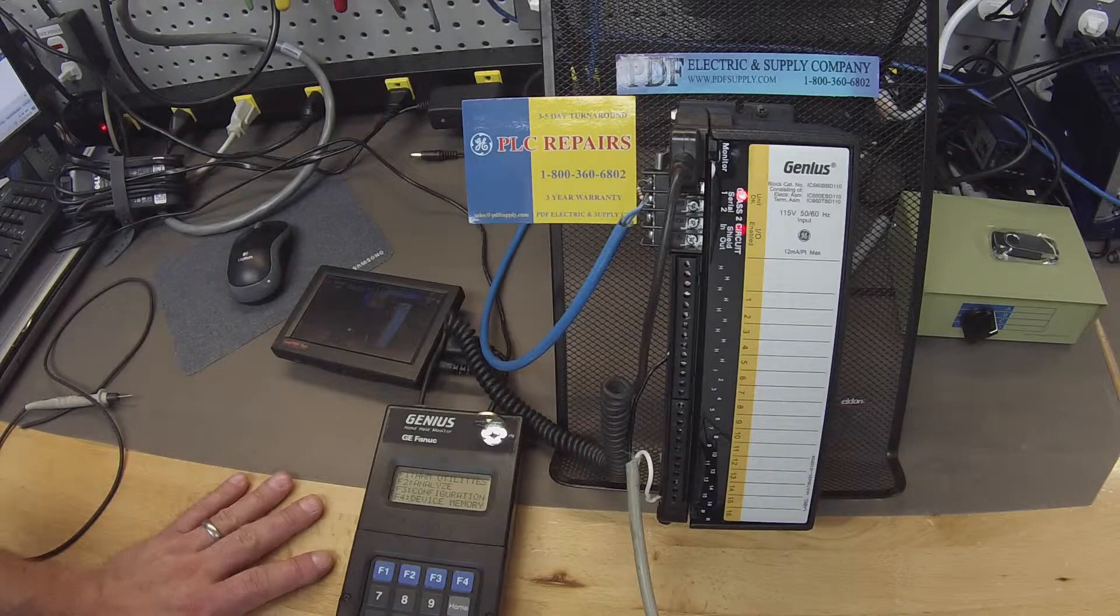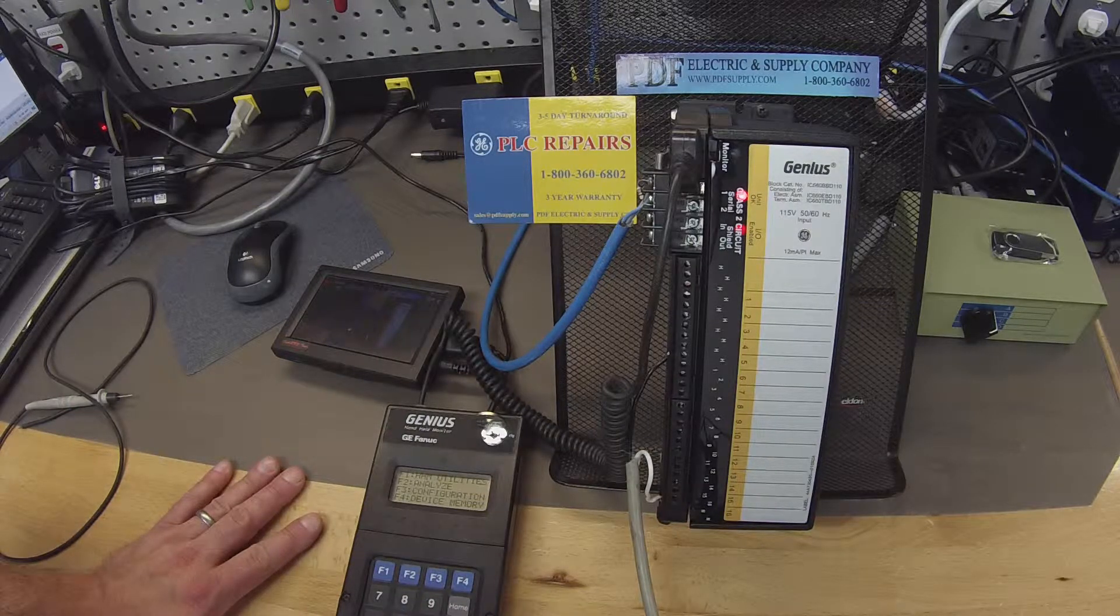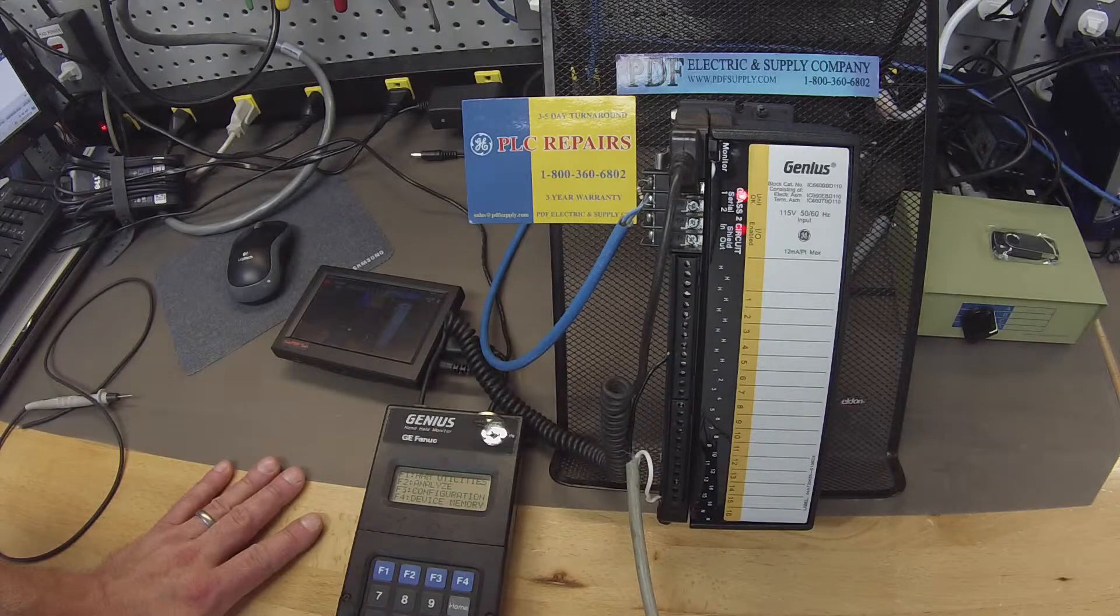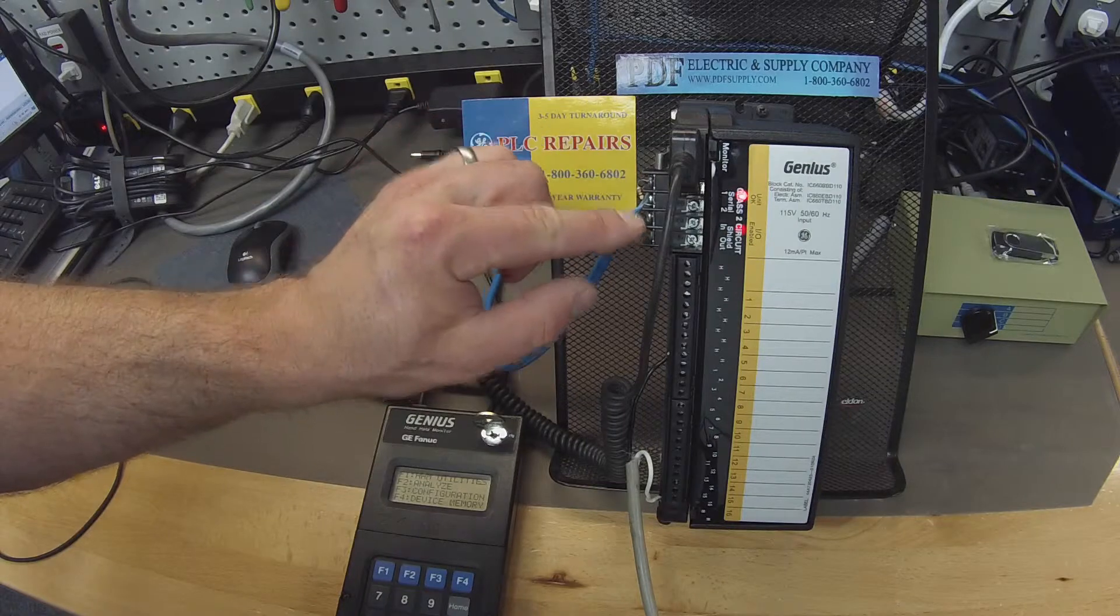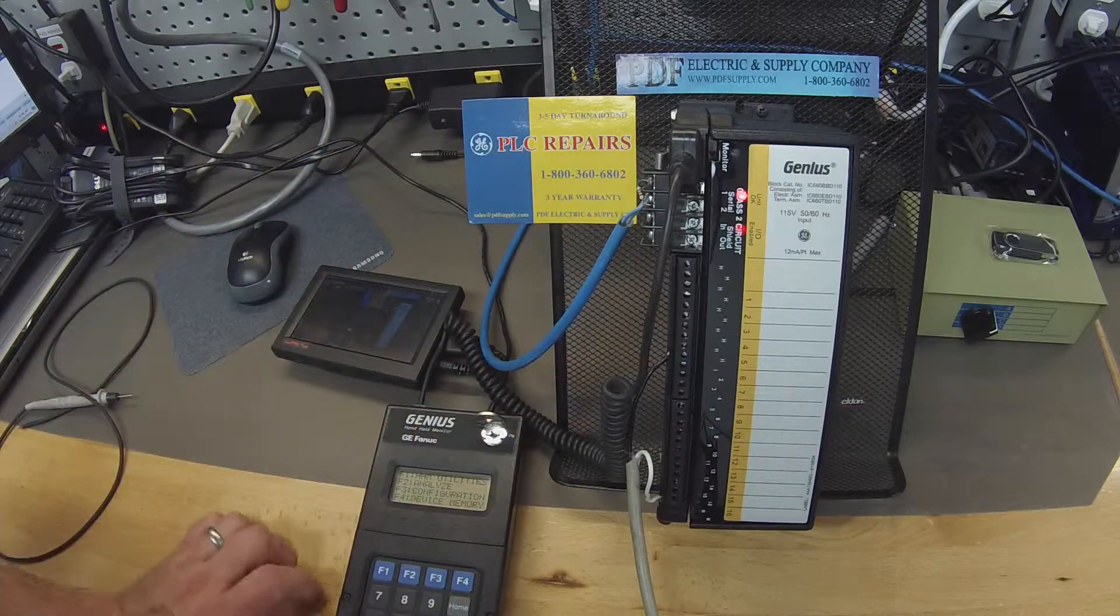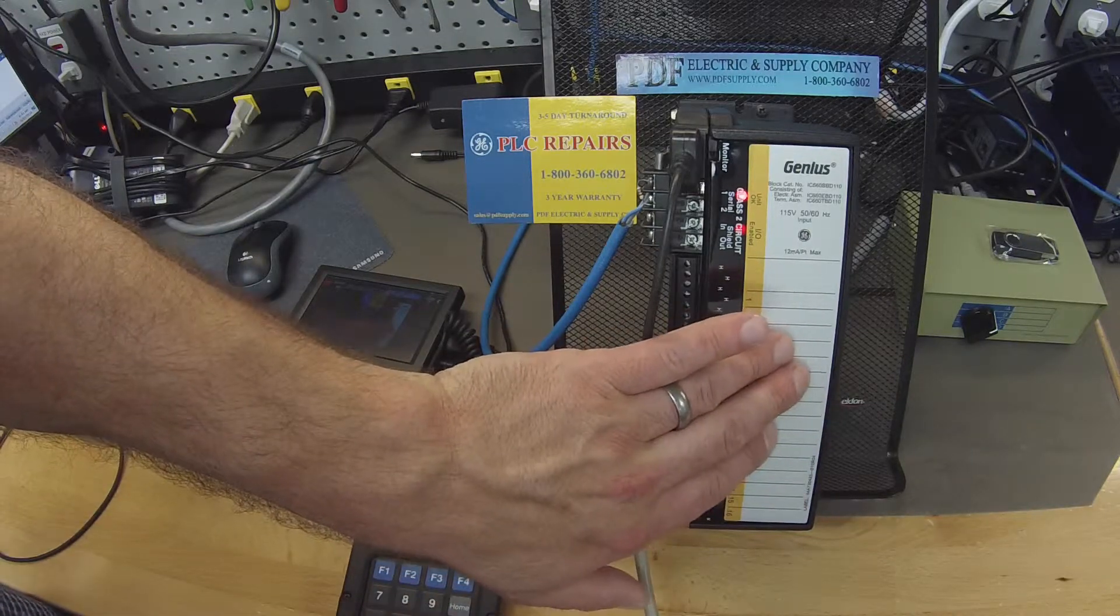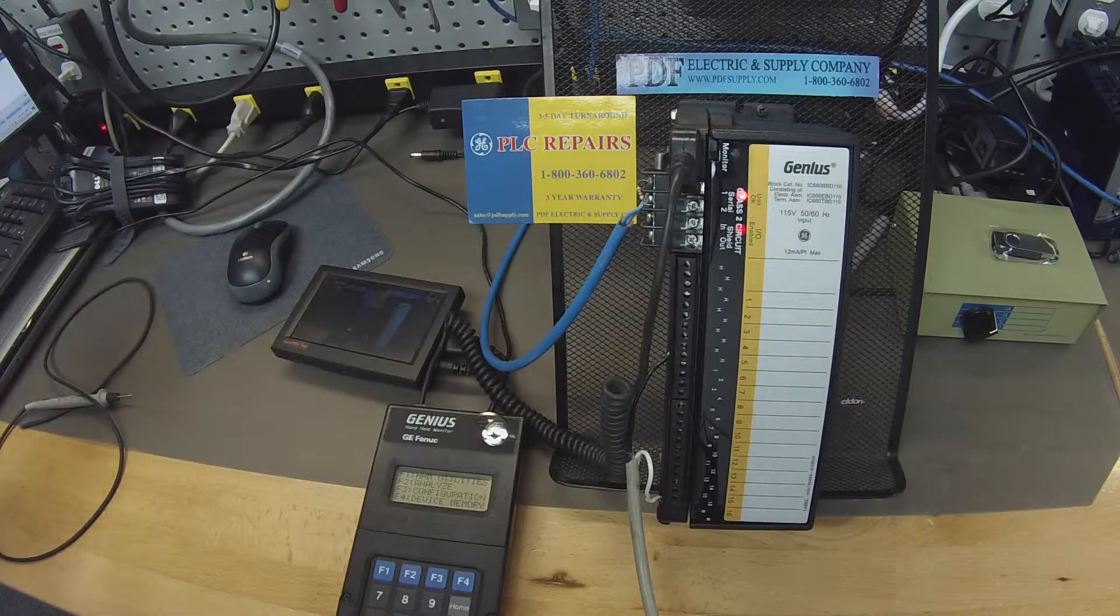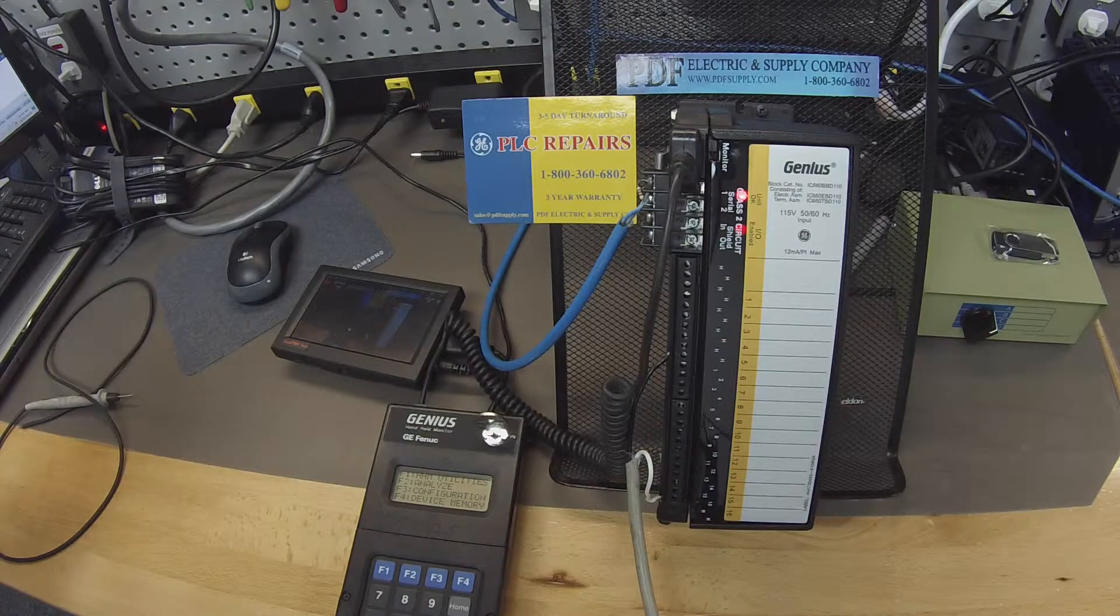Now, jumping back to the genius block for a moment here. This is part of the physical test, the actual probing of the inputs. Now, we have an IO enabled light on. That means that it's communicating with the genius bus controller, which is good. We also want to make sure that all the inputs that are related to this block at this address are also reporting in our input table on Proficy Machine Edition. That'll be the last step.